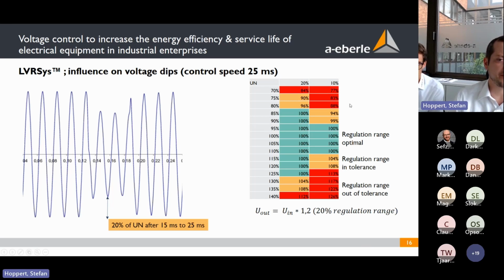If the voltage goes down to 75%, we can reach with our 20% system an output voltage of 90%. So 90% means we are back within the tolerance limits of plus minus 10%. That means with a 20% system, we can mitigate this voltage dip and bring it back to the limits. But here you can see if the voltage dip goes down to 50% and we raise it by 20%, then the resulting voltage will be 60%. So the lower the input voltage is, the less we can solve the voltage dip through our system. The system is made for voltage fluctuations, but if your dips are not going deeper than 75%, of course, then we can help.